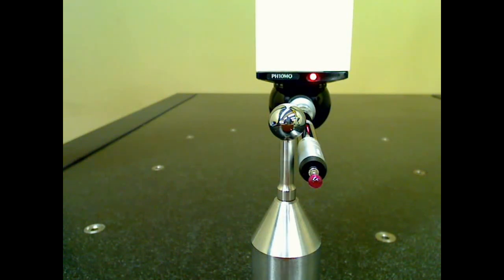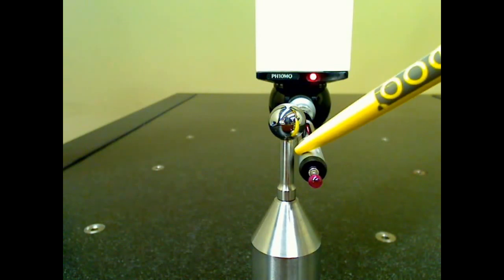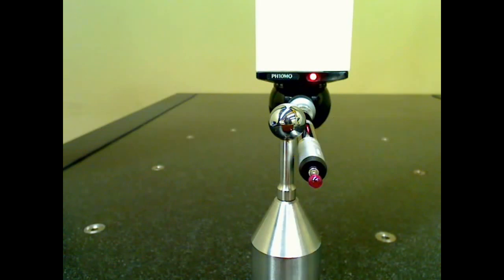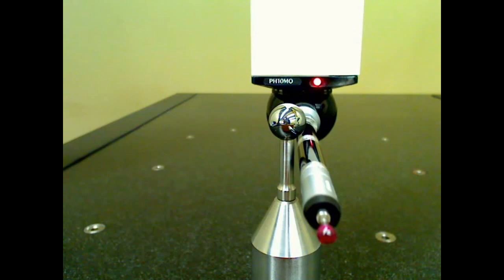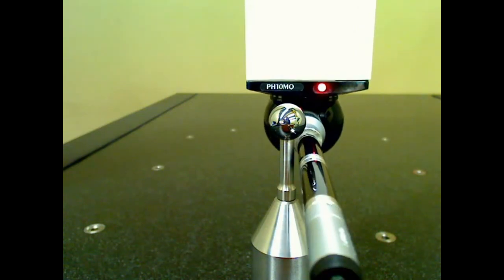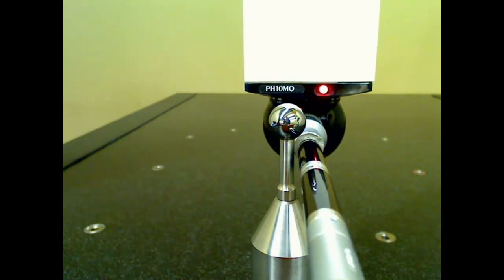So when I have the CMM x-axis locked, what I'm looking at is this gap between the sensor and the shaft of the calibration artifact. Now I'm just going to run the machine slowly from one end to the next and ensure that that gap does not change.